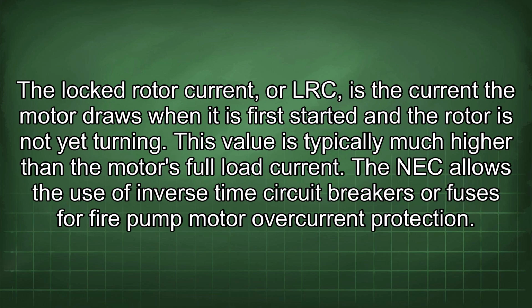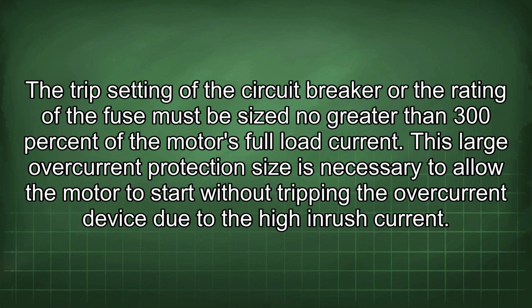The locked rotor current, or LRC, is the current the motor draws when it is first started and the rotor is not yet turning. This value is typically much higher than the motor's full load current. The NEC allows the use of inverse time circuit breakers or fuses for fire pump motor overcurrent protection. The trip setting of the circuit breaker or the rating of the fuse must be sized no greater than 300% of the motor's full load current. This large overcurrent protection size is necessary to allow the motor to start without tripping the overcurrent device due to the high inrush current.